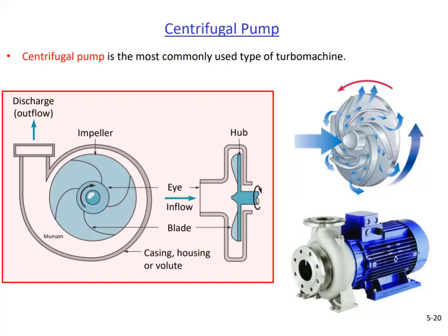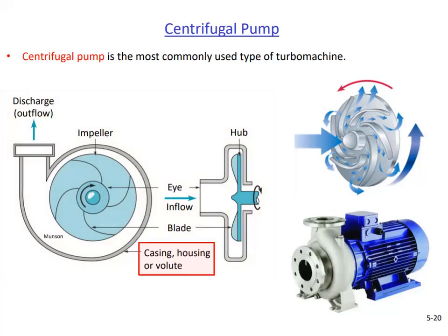Important parts of it are the outer casing, also known as the volute, the impeller disc, which is attached to the shaft and rotates with it, and the blades that are attached to the impeller disc. Flow enters the pump parallel to the shaft axis from the opening known as the eye. The inlet side of the pump is also known as the suction side. Flow exits the pump perpendicular to the shaft. The outlet of the pump is called the discharge side.